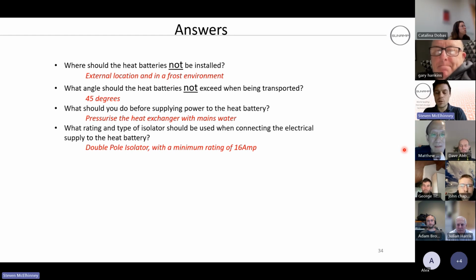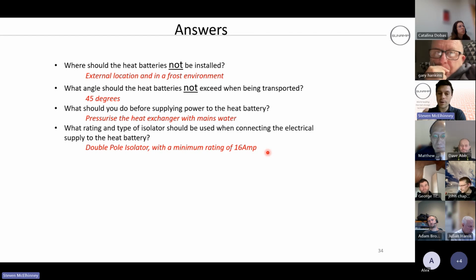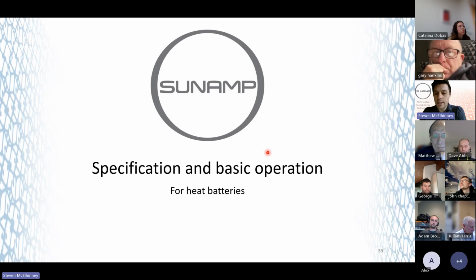This is quite an important one for me, because we do get some jobs where installers have used a 13 amp fuse spur. But because we'll pull about 12.5 to 13 amps, we're just touching the maximum rating of the fuse spur, and what can happen is it can scorch itself, become brittle and burn itself out. So you've got to up it. All right, so good stuff.